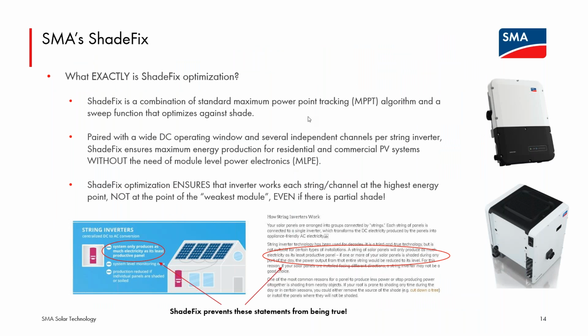I want to segue a little bit into discussion of rapid shutdown and ShadeFix. So again, ShadeFix is an optimization technology built into SMA's residential Sunny Boy line, as well as our commercial CORE1 line. So we're showing both icons here. The discussion is the same for both product lines. We at SMA, we're celebrating our 40th anniversary this year. We feel we are pretty good at building very full-featured inverters, and we think it is best for the system to leave as much functionality as possible in the inverter itself. If something goes wrong in a system, a service technician has to go out to visit the system, we want them to be able to access the inverter to resolve the vast majority of those issues. The inverter should be in an easier place to access in most scenarios rather than having to dig apart the array to replace a failed module level power electronics device. So as much functionality as we can leave in the inverters, we would like to.